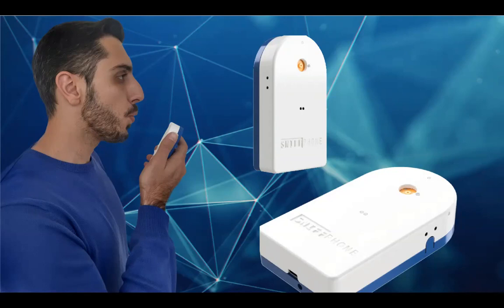And therefore, we train it on different populations. We store the data, and the blind analysis will, of course, be compared with the memory that we have. This is something that we know with mass spectrometry, actually, but today we do it also with this very miniaturized device. It's very important to note that one of the most important parts of this device is when you capture the breath, because you have the so-called dead space and alveolar breath, and we need to take the breath from the lungs in a non-invasive way. And therefore, the timing of when to detect with the device is really very important. And therefore, there is a very small sensor here that measures humidity and CO2 from exhaled breath with very high accuracy.